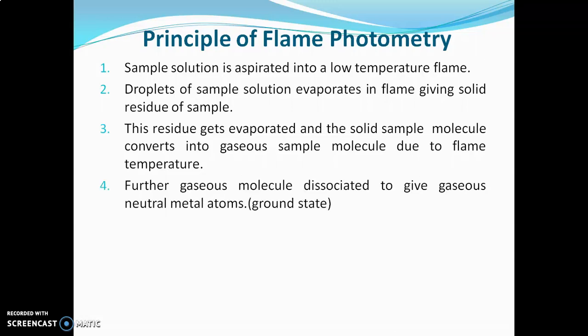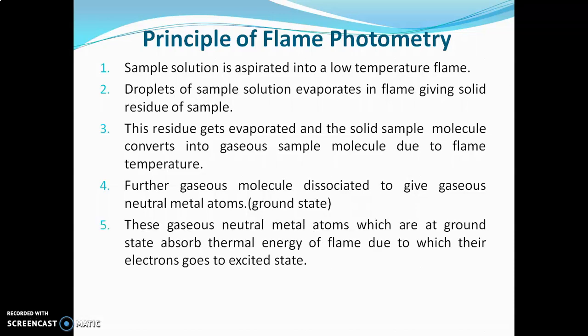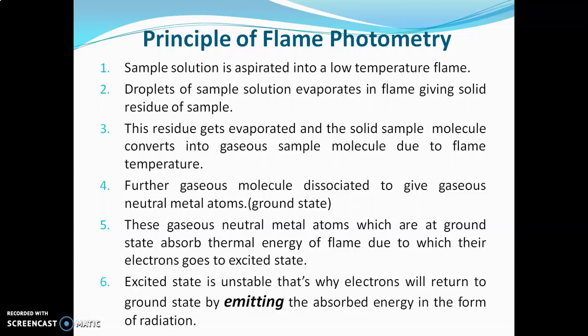These gaseous molecules dissociate to give gaseous neutral metal atoms, which are at the ground state. These ground-state gaseous neutral metal atoms absorb thermal energy of the flame, causing their electrons to go to the excited state. Since the excited state is unstable, the electrons return to the ground state by emitting the absorbed energy in the form of radiation. These emitted radiations are the basis of flame photometry and are measured by a detector.